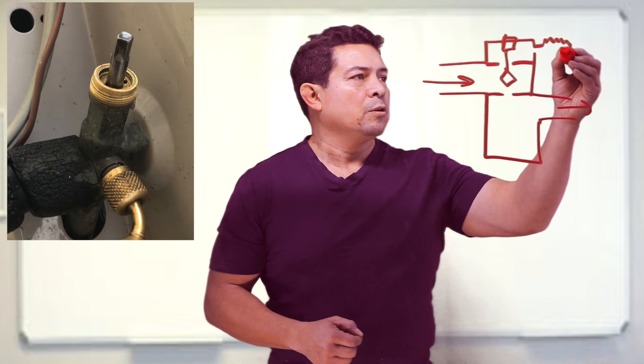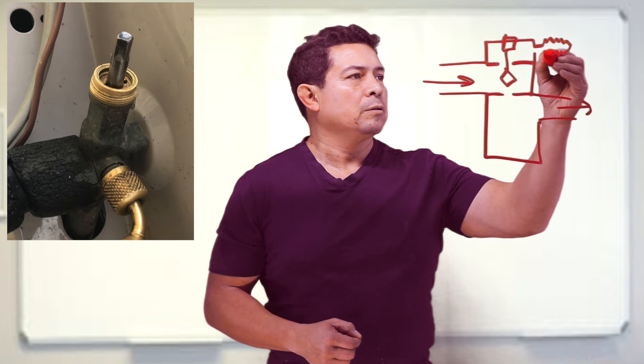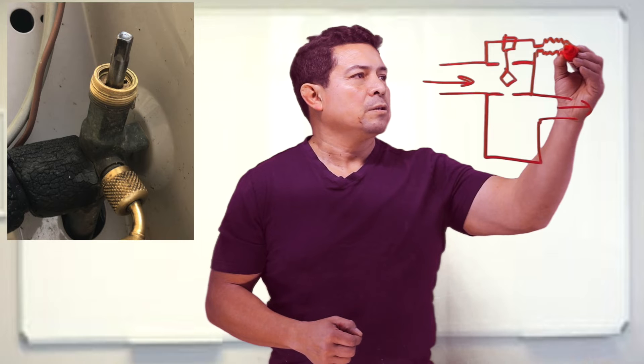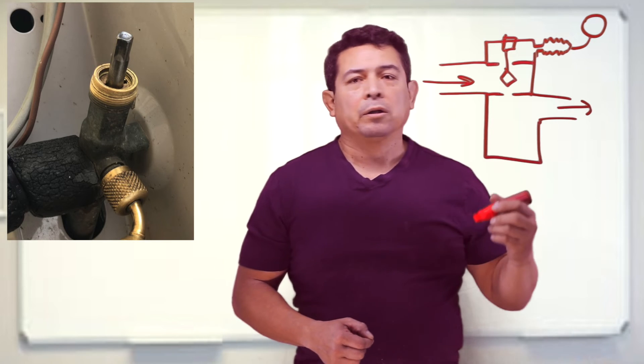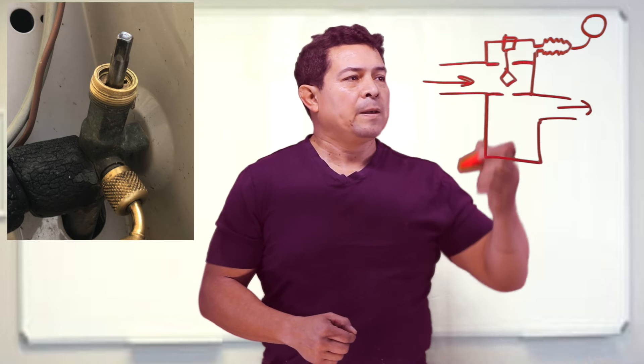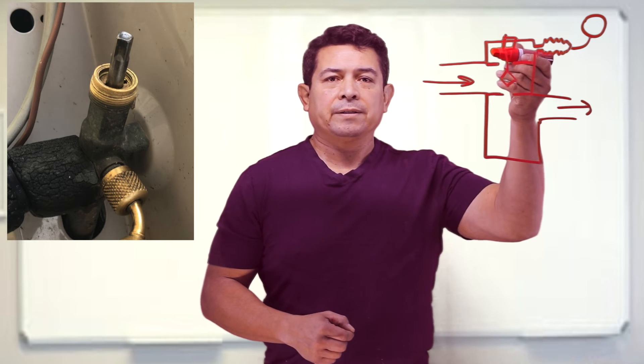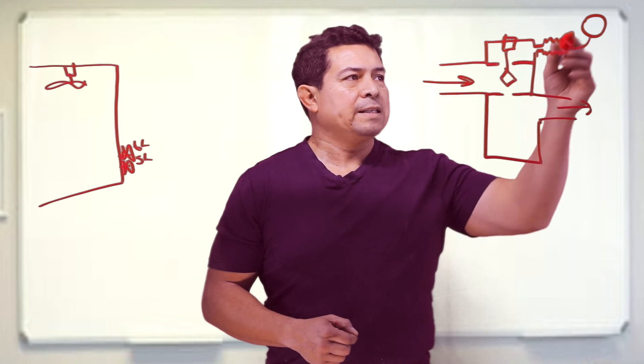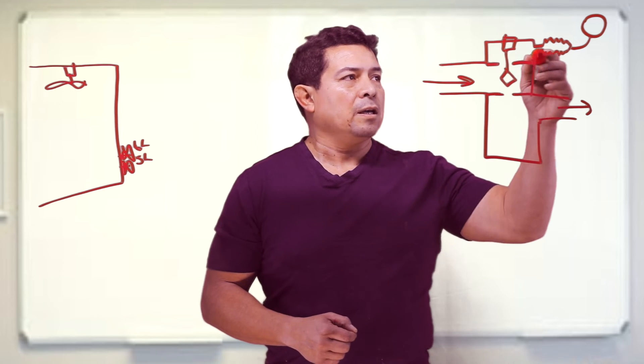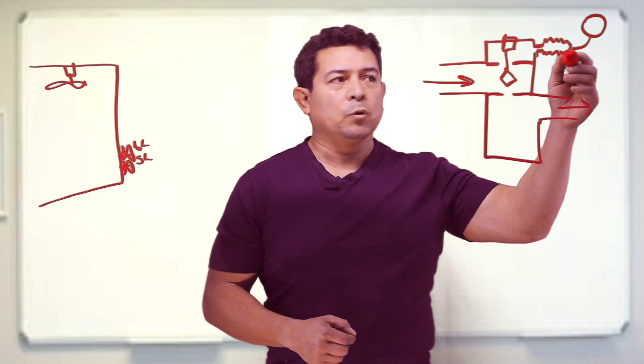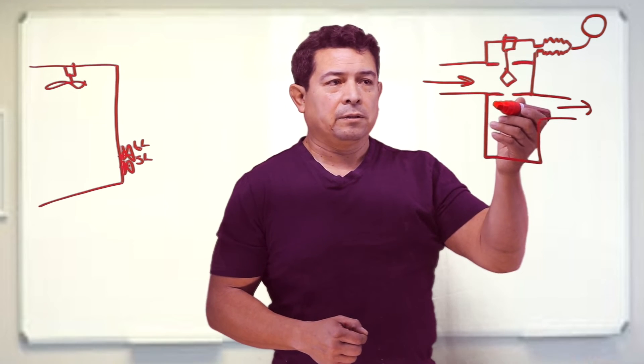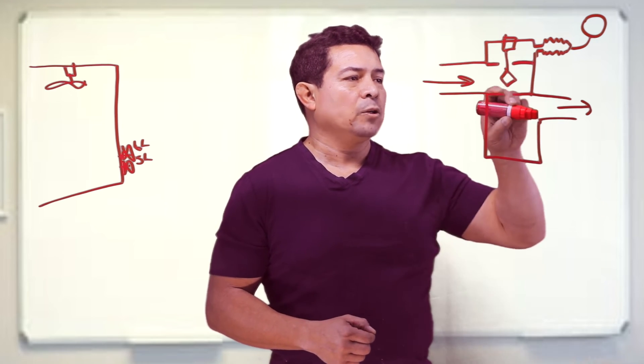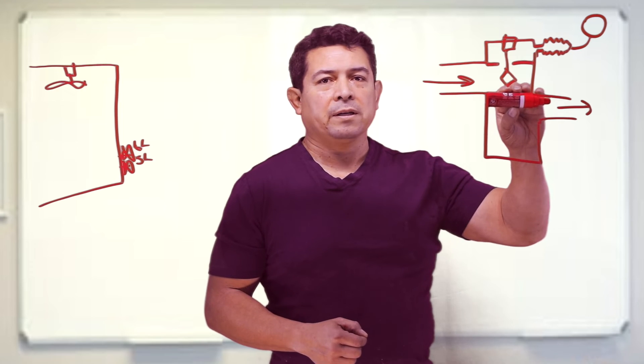So we actually hook up our high side gauge or our low side gauge right here. So if this is all the way back then you're going to isolate this and you're not going to get a reading. You won't be able to add refrigerant to it. If you have it all the way down then there's not going to be any flow because you have stopped it right here.